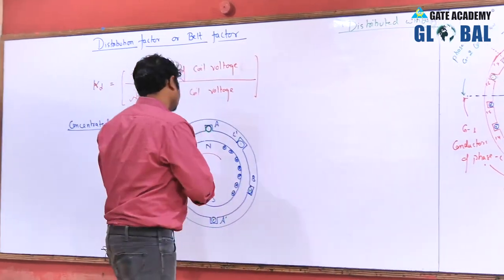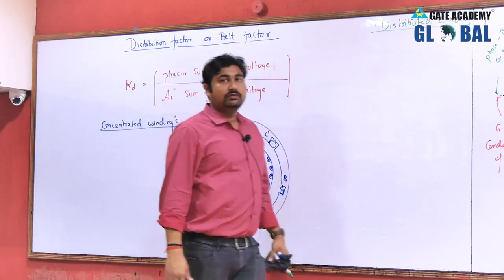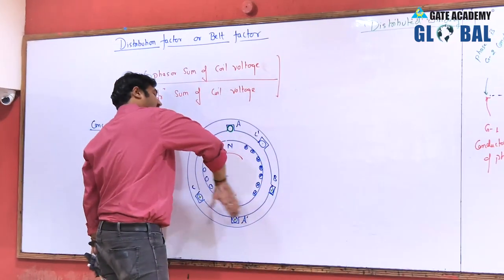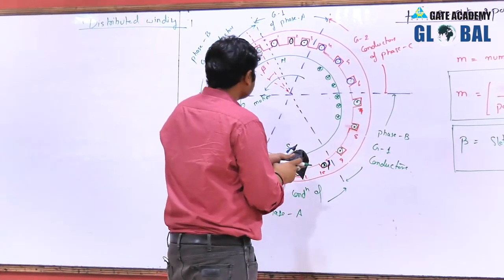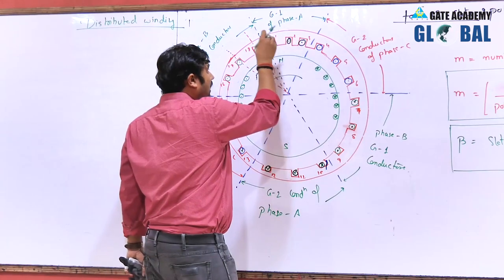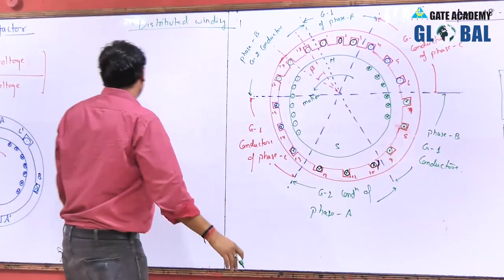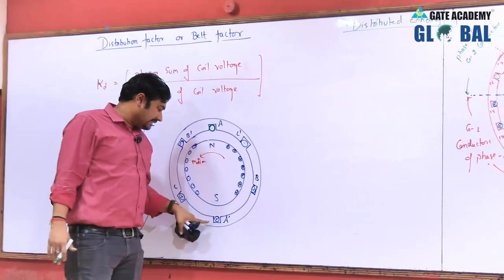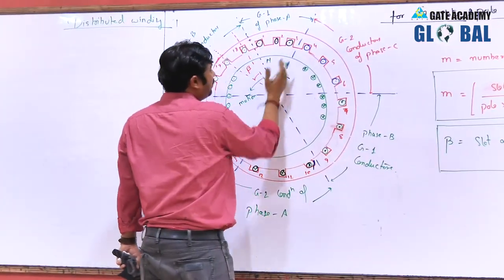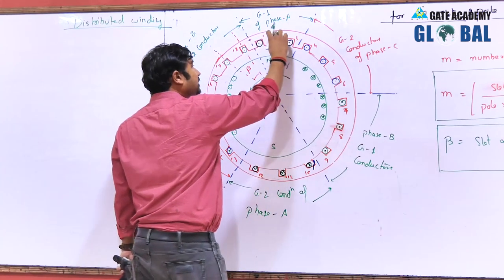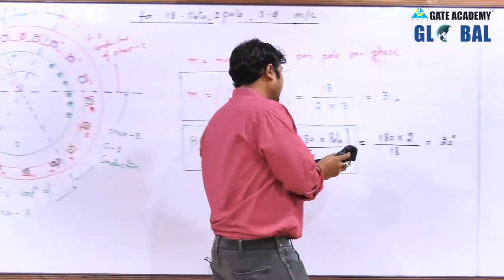For concentrated winding, arithmetic sum and phasor sum are the same because all A phase coils are concentrated in a single slot. However, in distributed winding, A phase is spread across multiple slots, so voltages generated in each conductor are phase-displaced by angle beta. This can be understood through the EMF polygon formed by the phase. The voltage generated in conductor 2 becomes maximum after beta degrees of rotation from position 1.